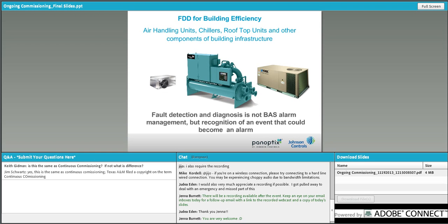So FDDs combine data from multiple sources to infer events or patterns that suggest more complicated circumstances. Another example is the FDD for an air handling unit. It may take into account set point, discharge air temperature, duct static pressure, damper position, zone temperatures, all these different points, and determine what the possible problem could be based on the position of all these different points in a system.